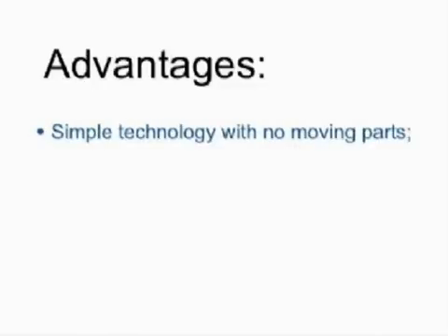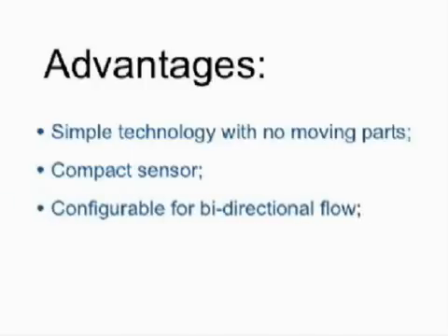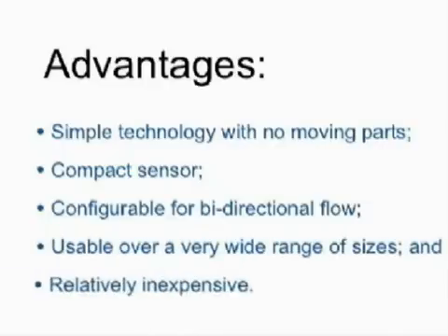There are many advantages to this approach. It's a simple technology with no moving parts. The flow measuring sensor can be very compact. Depending on the configuration of your pressure sensor, you can set it up for bi-directional flow. The approach is scalable over a very wide range of sizes, and it's relatively inexpensive.